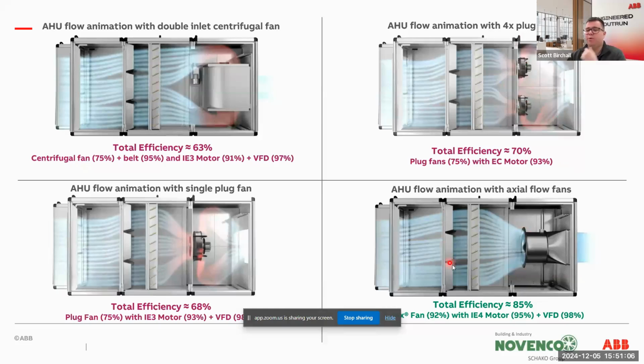What we're seeing more recently come to the market is axial fans. And one of the OEMs that we've been working with a lot, who are one of the market leaders, is Novenco. As you can see, the axial fan is a little bit different to these other ones. There's no need for a wall or any ducting. It just operates into the open air there. And you can see the fan, motor and drive together running about 85% efficient.